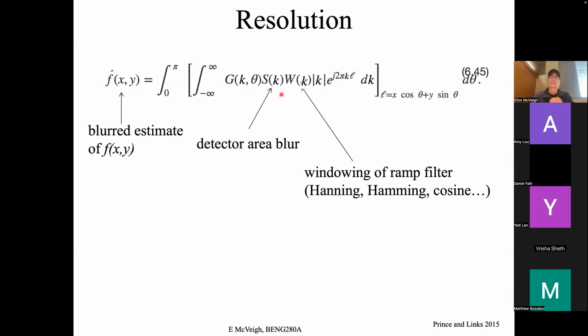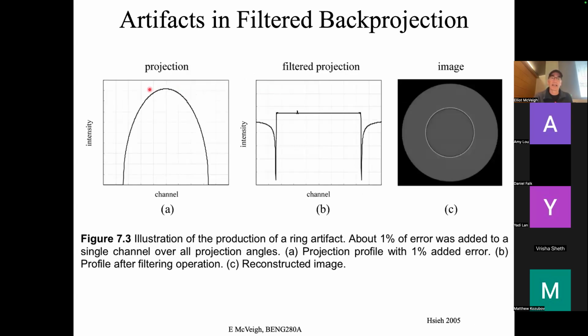If we look back at data that we have, along here is L, and I sample that function with a separation that is given by the separation of my detector elements. So in a modern CT scanner, most of the time, those detector elements are 1 millimeter apart, and sometimes they are 0.5 millimeters apart. That's in an energy integrating detector; the Canon high resolution scanner has detectors that are 0.5 millimeters apart, which was a big leap in technology about 5-10 years ago.